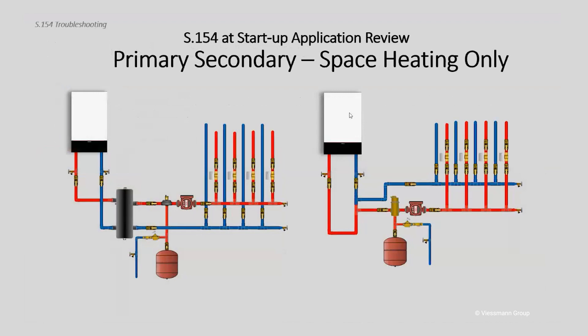First thing when looking at a hydronic system: it's important to get the air out of these heating systems before we fire that boiler up. Often what guys will do is install the boiler, fill and vent everything, get the pressure up, turn the boiler on, and do commissioning. With these new 100s and 200s, I recommend you do the final phase of filling and venting or air purge with the boiler on during commissioning — that's the important thing to note.